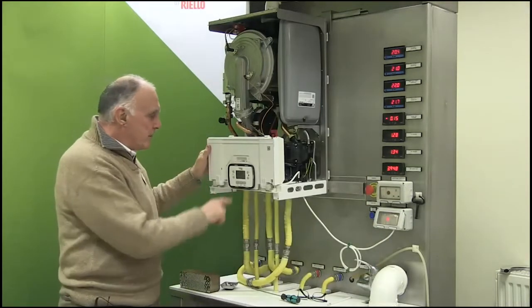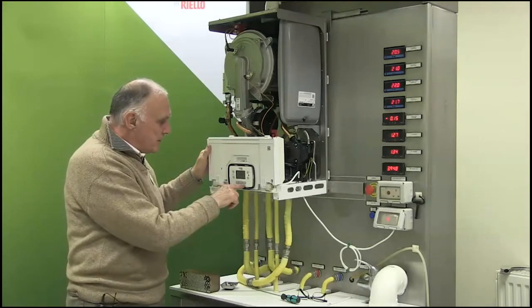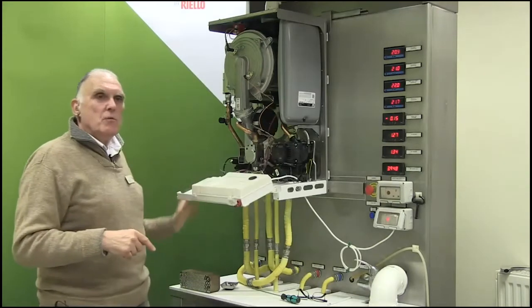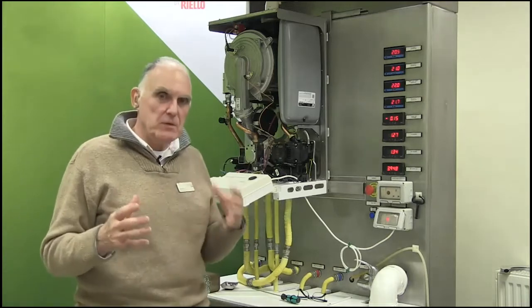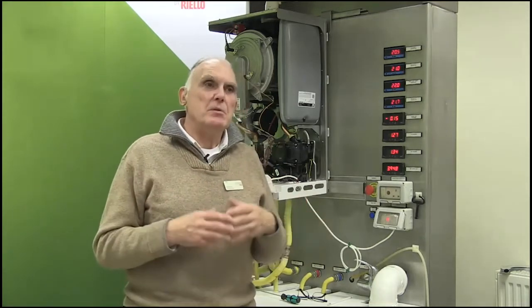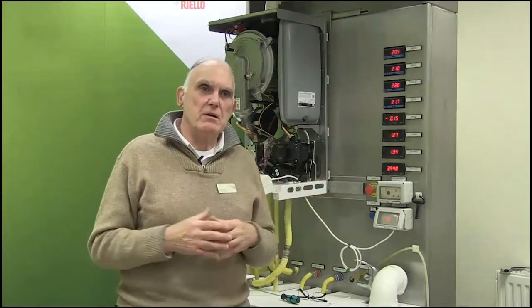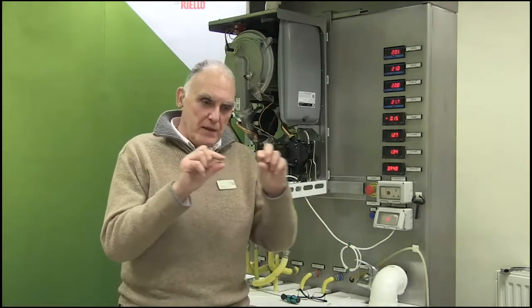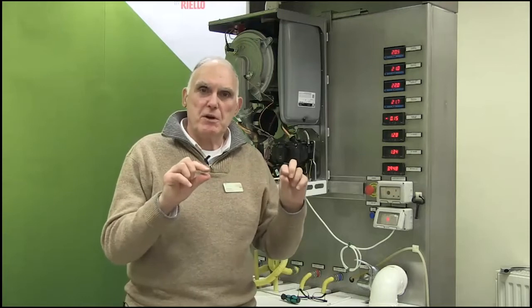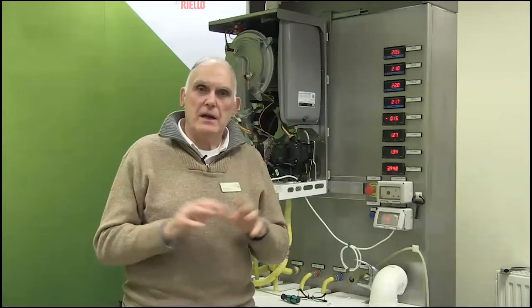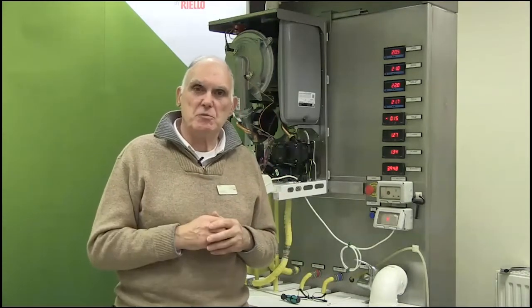So you just power up, but there's a button in the middle of the lower three called reset. While it's in purge, first fill, let it do its purge. But subsequently, if you've turned the boiler off and turned it on, it will show you a little display at the bottom saying air purge in progress. Simply press the middle button, reset button on the bottom row of buttons, and it cancels purge. So it's very easy to cancel purge. I'm going to take you through combustion analysis. So if you could bear with me for that, I'll show you how to do that.